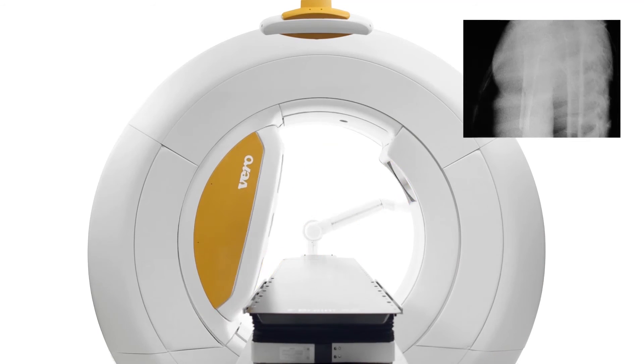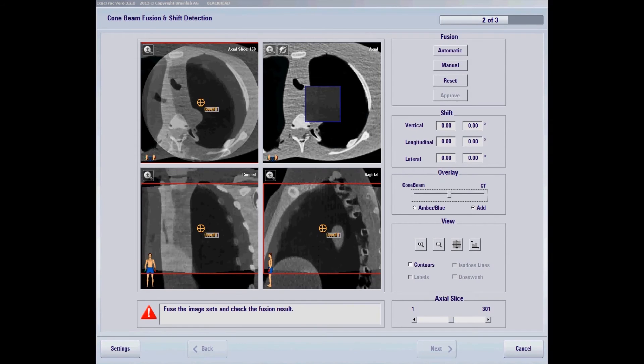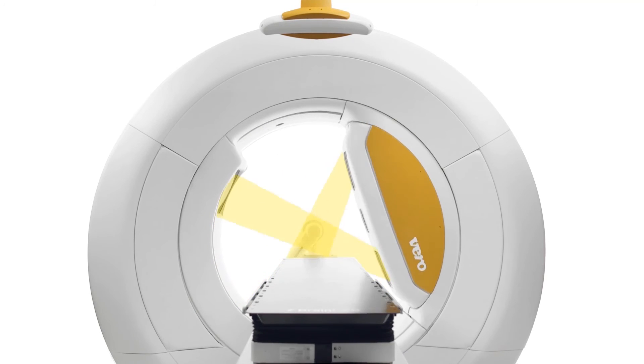Its unique ring architecture allows for verification any time during beam-on, even at rotated gantry and ring angles. Soft tissue imaging can be done before each treatment with cone beam CT. Since Vero integrates two independent diagnostic imaging systems, it is possible to speed up imaging time and have reconstructed images available in less than 30 seconds. The stereo diagnostic imaging system also presents the option of dual energy cone beam CT to further increase image contrast and quality.